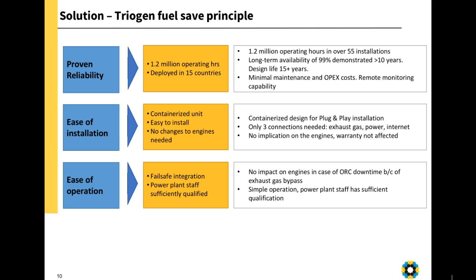It's got a fail-safe mode where, if the ORC is down because of maintenance or, God forbid, an error, the generators and engines can continue running normally. They don't see any difference. The default setting is that the flue gas escapes and doesn't have any implication on the engines.